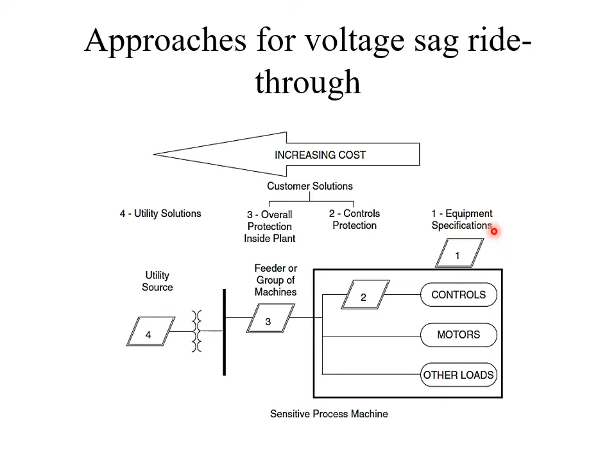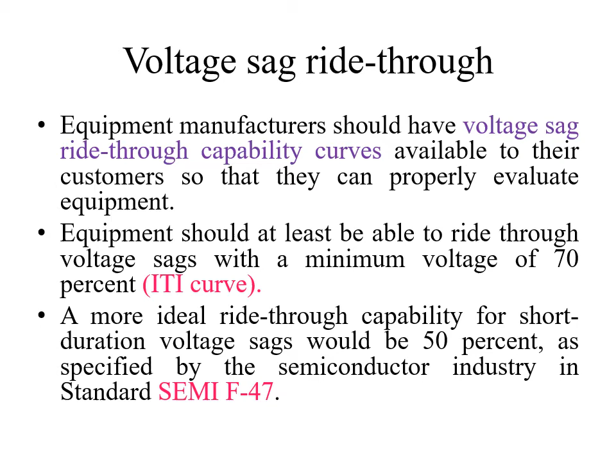The manufacturer should have the voltage sag ride through capability curve to manufacture the equipment, so that it can be properly used. The equipment should have at least 70% voltage ride through capability, as per the ITIC curve. The more ideal ride through capability for short duration voltage sag would be 50%, as specified by the semiconductor industry in standard SEMI F47. The solution at the higher levels, that is at the utility level, generally becomes more costly, so it is preferred to do solutions at the manufacturer level.